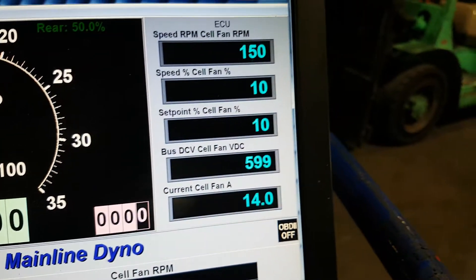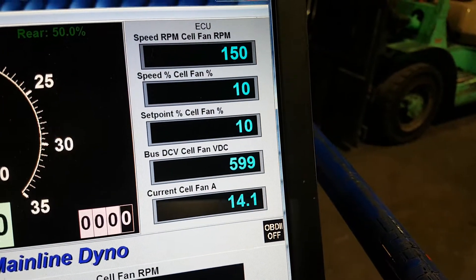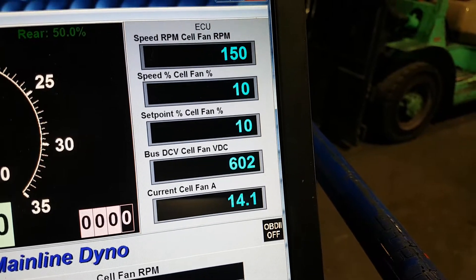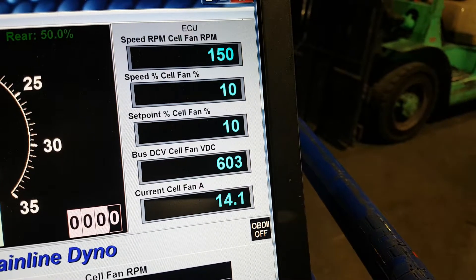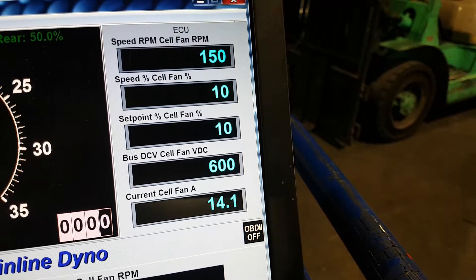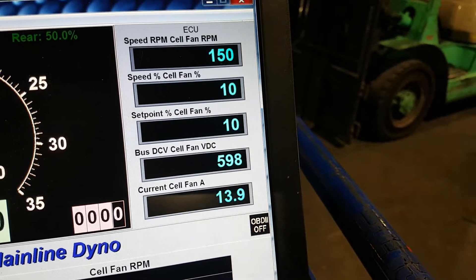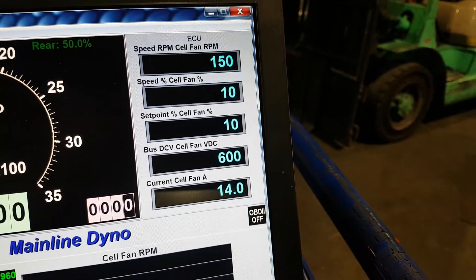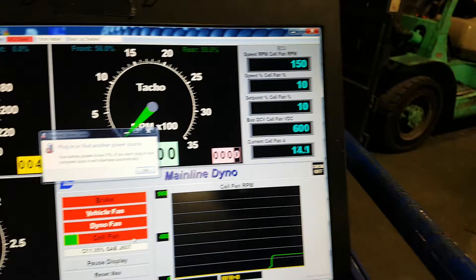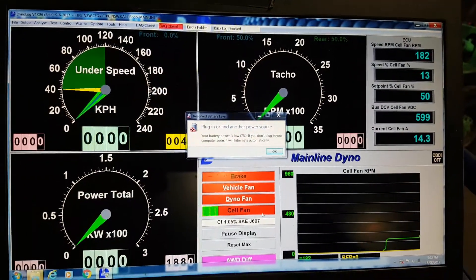At the moment it's still drawing about 14 amps, because it's quite a large fan, doing 150 motor RPM with the set point at 10%. We also get what's called a DC bus voltage coming back from the VSD. Now we'll hit it up to the faster speed and we'll see things change.